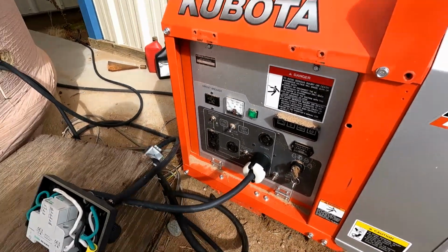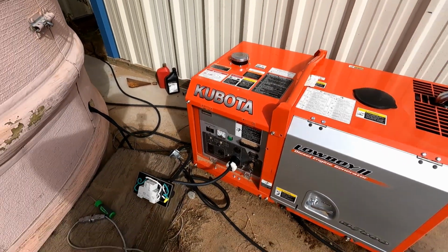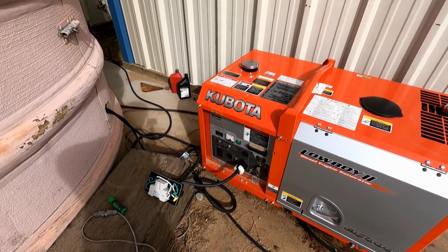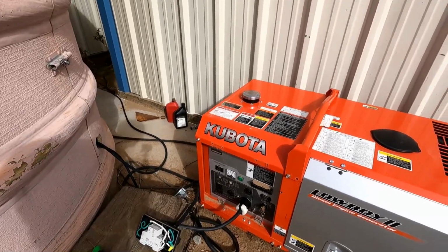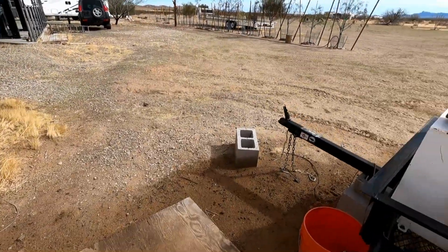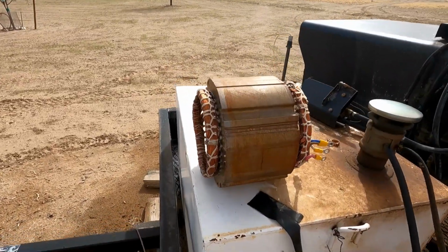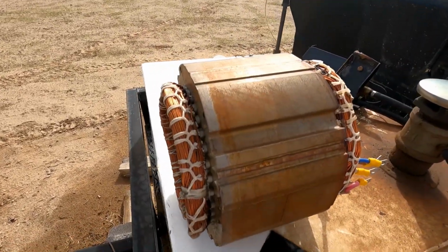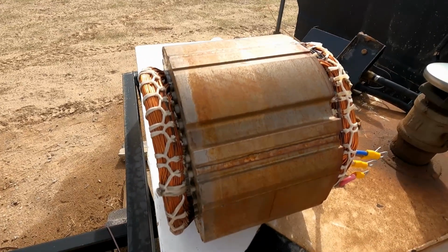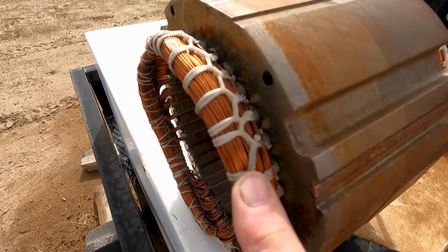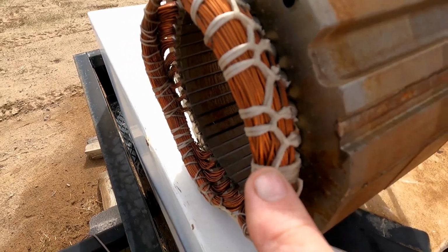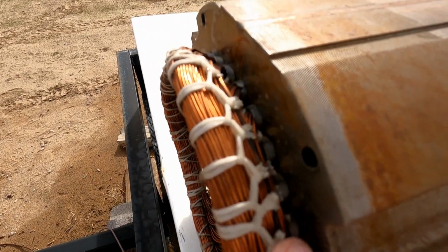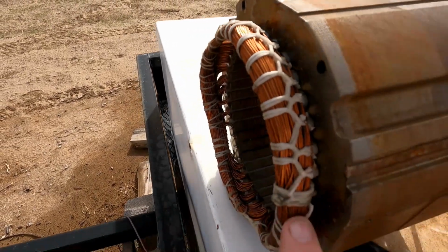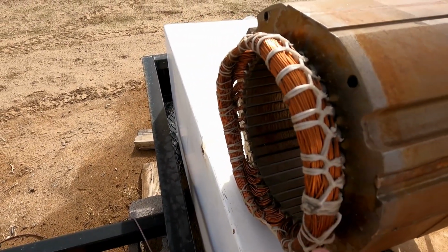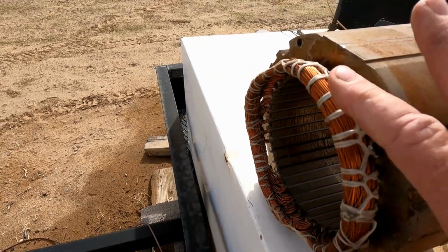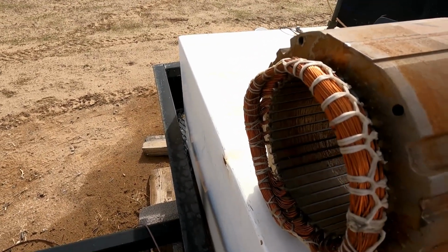And it's often felt that the generator probably has the ability to absorb that, and arguably up to a point the generator does. But let's look a bit at the internal construction of the generator, where your generator voltage is coming from. And that's this stator right here. And on this stator you see that the windings have a lacquer insulation on them, and where they pass through the stator they have these little plastic sleeves to insulate them from the stator. And all that's necessary because the stator is grounded and the voltages coming out of here are not grounded.